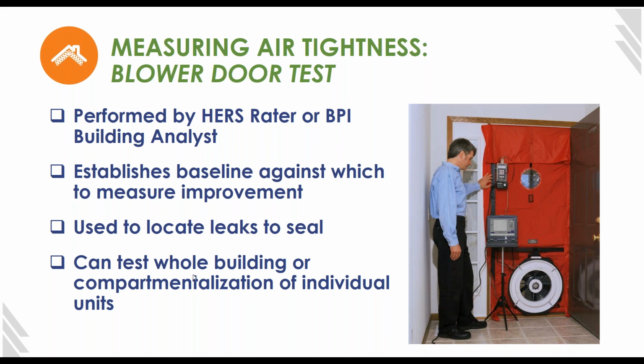With a blower door test, you can test a whole building. In the case of a single family home, that's generally how it's done, or you can test for compartmentalization of individual dwelling units in a multifamily building. Compartmentalization is pretty commonly done in multifamily. Whole building testing is not as commonly done, but it is growing in popularity. You do need a building with interior corridors — a garden style building with exterior walkways wouldn't be testable as a whole building, only by compartmentalization.